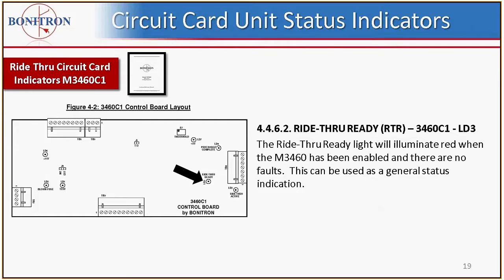Also on the C1 card is the ride-through ready indicator. The ride-through ready light will illuminate red when the 3460 has been enabled and there are no faults. This can be used as a general status indication because most of the faults feed this light. So if this light is out, the manual will tell you some of the reasons that the ride-through ready light does not light properly.